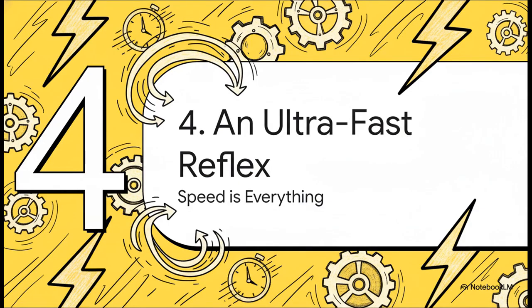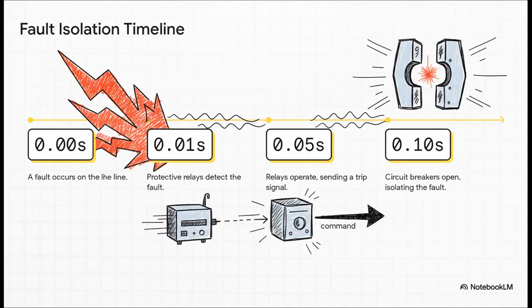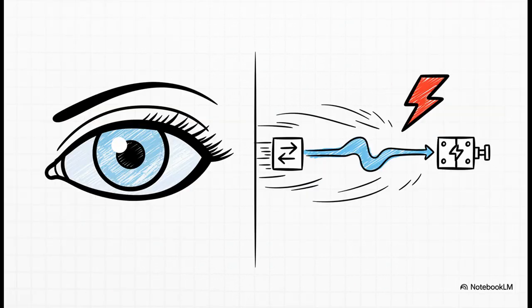We've talked about how precise this system is, but the other critical element here is speed. This isn't just a response, it's a reflex, and it operates at a truly mind-boggling pace. Okay, check this out. The response is practically instantaneous. The moment a fault occurs, the clock starts. Within just 1/100th of a second, the relays detect the problem. By 5/100ths of a second, which the source calls high-speed operation, the relay has already made its decision and sent the command to trip. And by 1/10th of a second, these massive circuit breakers have swung open and the danger is completely over.